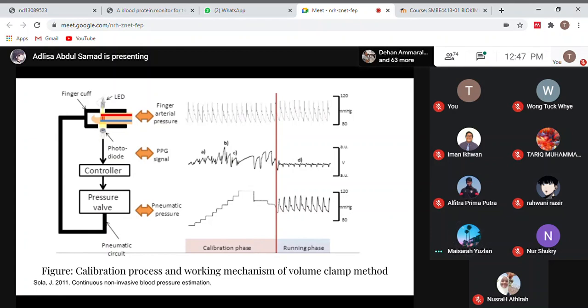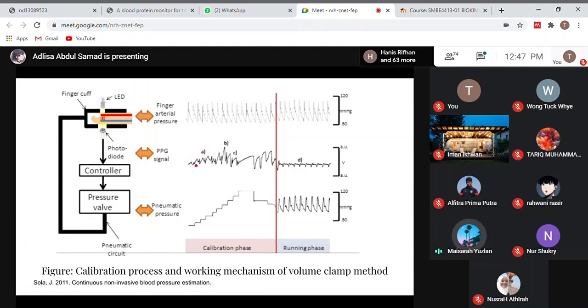So there are sections here: A, B, C, and D. Let me explain one by one. In A, the cuff pressure is smaller than the arterial pressure. That leads to small PPG pulsatility, which means the PPG signal is small, which we don't want. So in part B, the cuff pressure reaches the arterial pressure, which means the dynamic value of the pressure valve is reaching the value of the arterial pressure.